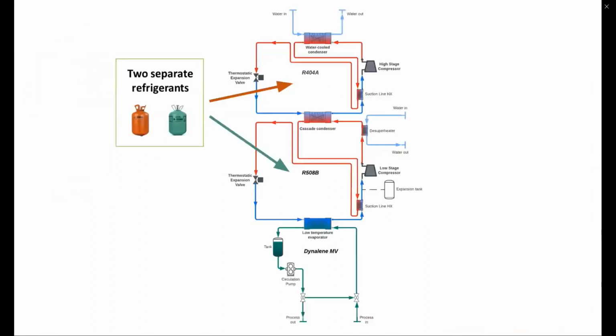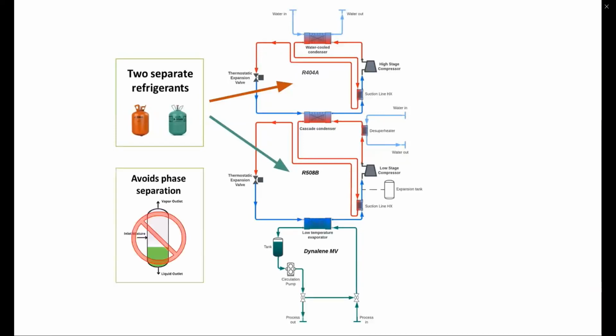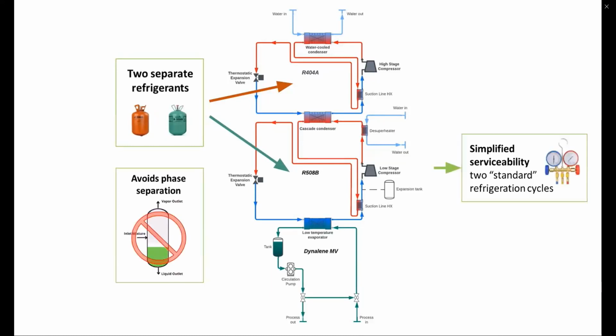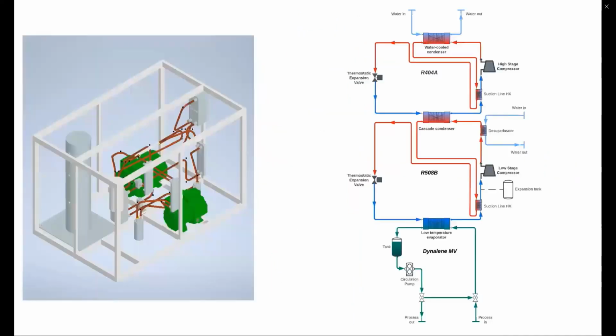Our solution is a dual-stage cascade system, providing an alternate to auto-cascade that improves upon current shortfalls, and reliability and maintainability are improved. The high and low stages work in series, with the high stage providing the cooling necessary to maintain an efficient operation of the low stage, which then in turn chills a circulating process fluid. Both the high and low stages utilize a conventional refrigeration cycle with a few improvements to increase efficiency.